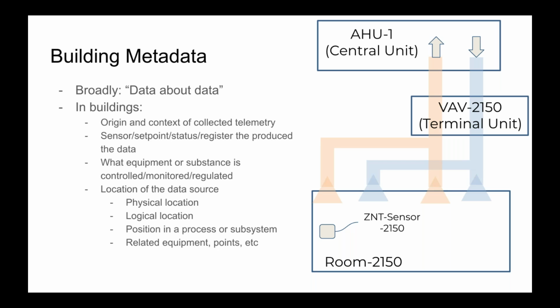the logical location, its position in a process or subsystem, and related points and equipment. We can imagine a zone temperature sensor: it only has significance in the context of everything around it. It's in a room, that room is in an HVAC zone, that room has return and supply dampers feeding air through a VAV box, and there's fans, pumps, and an air handling unit at the top. When we only look at the sensor, all the rest of that is implied.